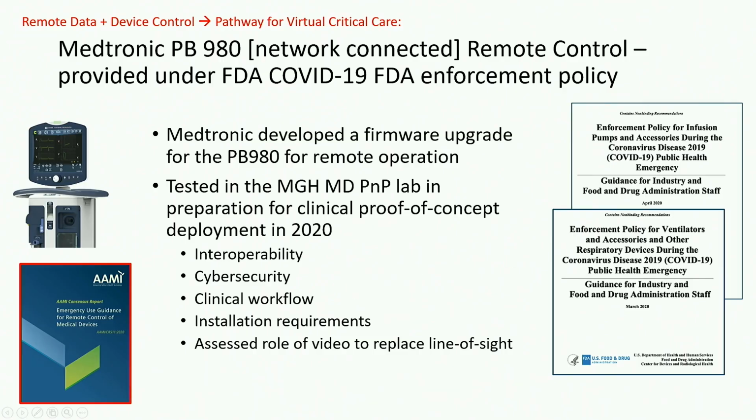As you see on the right, the FDA released what they call an enforcement policy, or immediate-in-effect guidance, in 2020 that said, if you have a product on the market and you want to add remote control to the product, you are allowed to do it, if it's a ventilator, an infusion pump, or a monitor. And so Medtronic added remote control capability for the PB980, and this also conformed to a standard that we developed. It was an emergency standard that we developed within AAMI, and these are freely available online, by the way, these standards from this era.